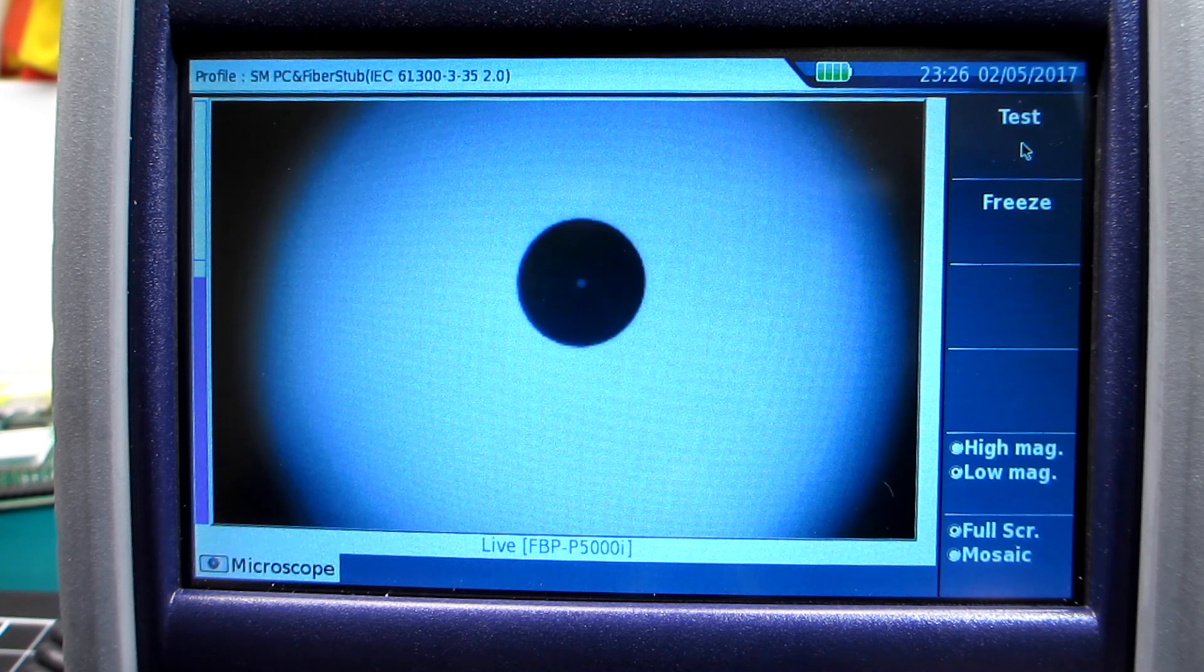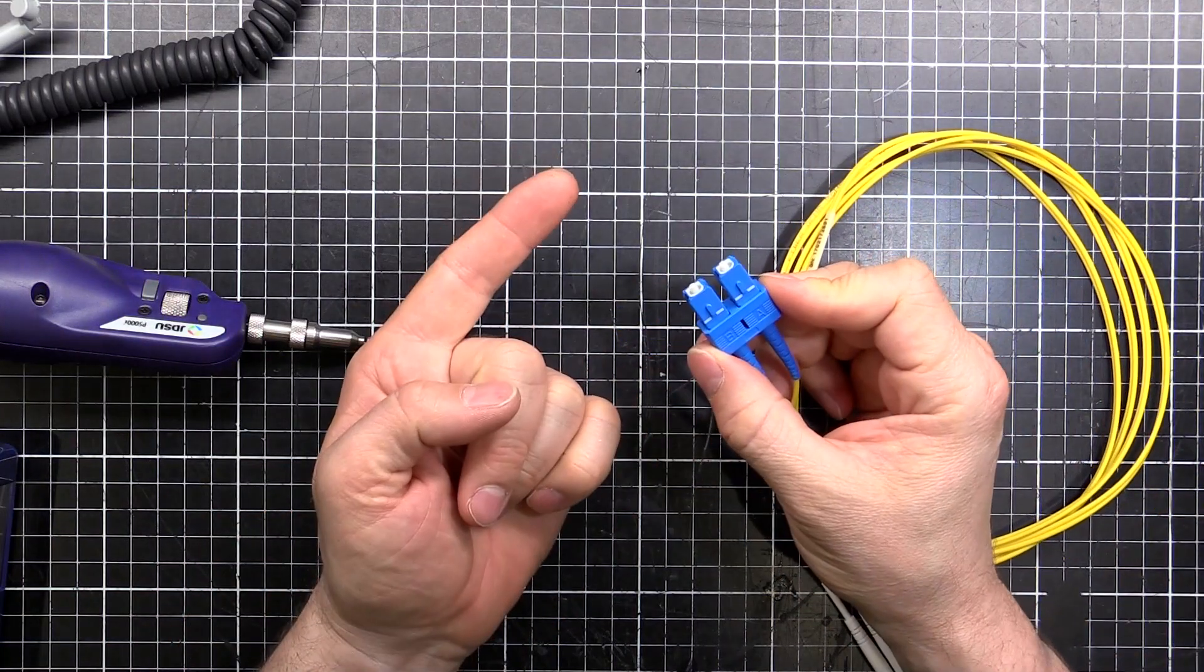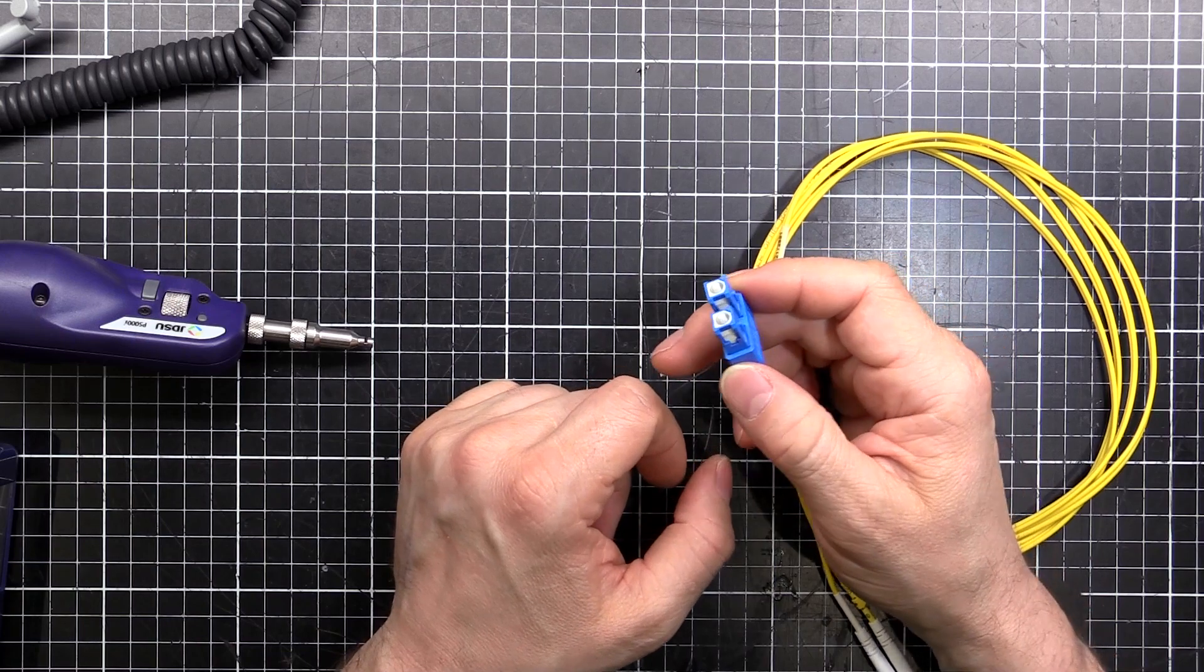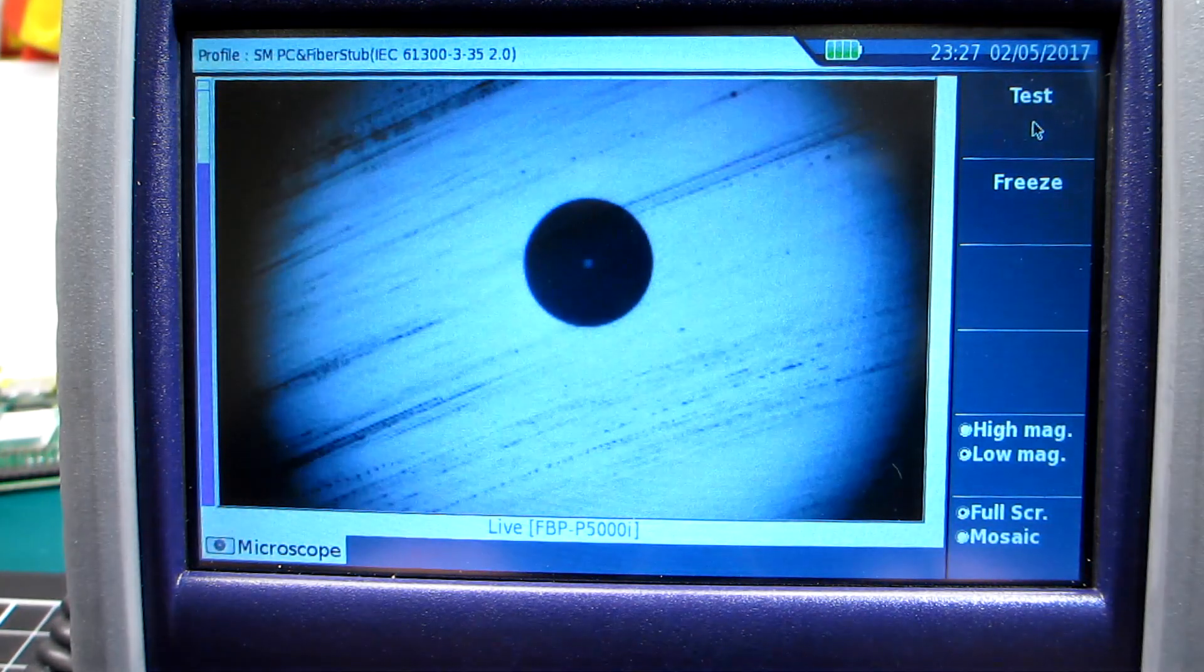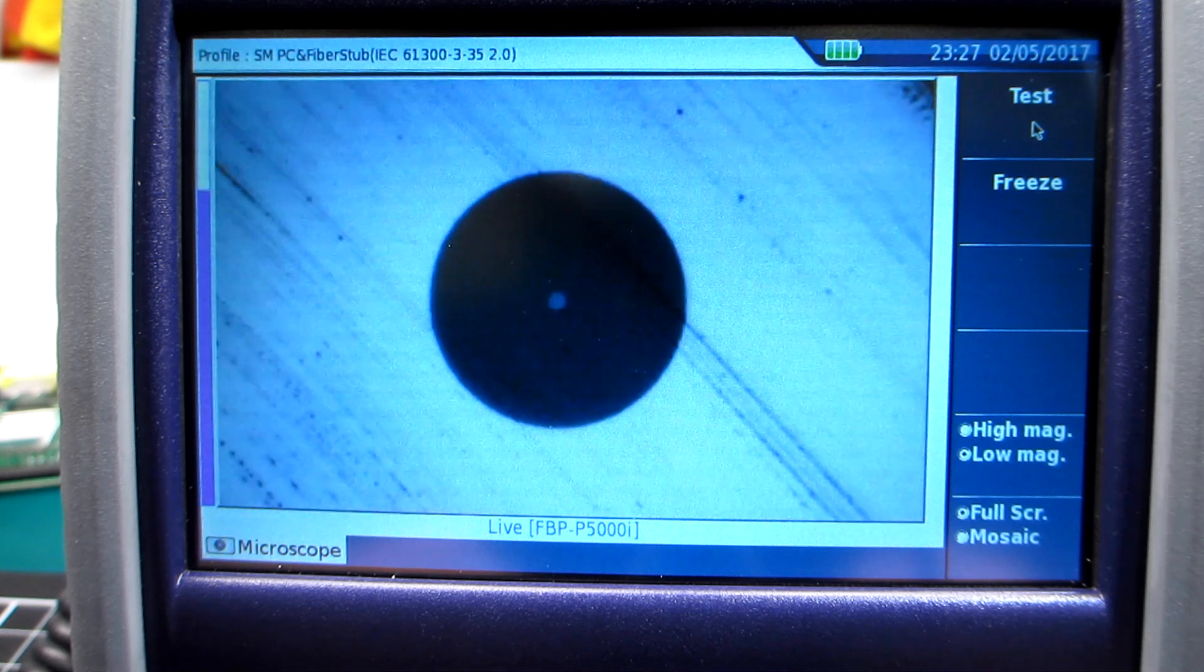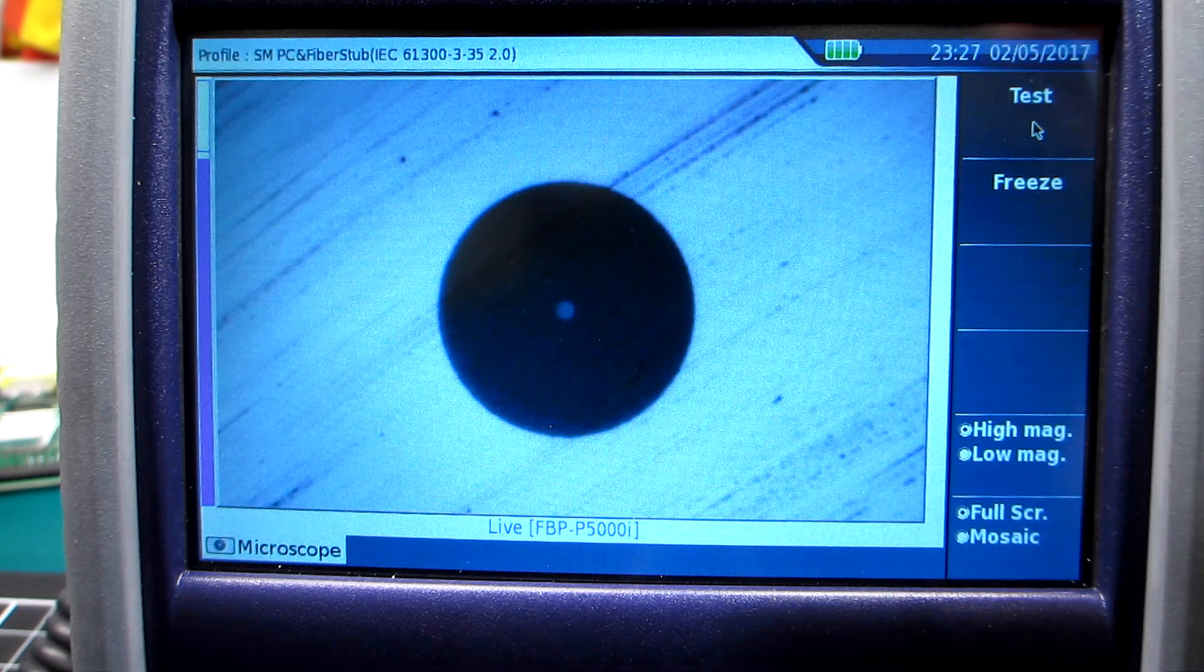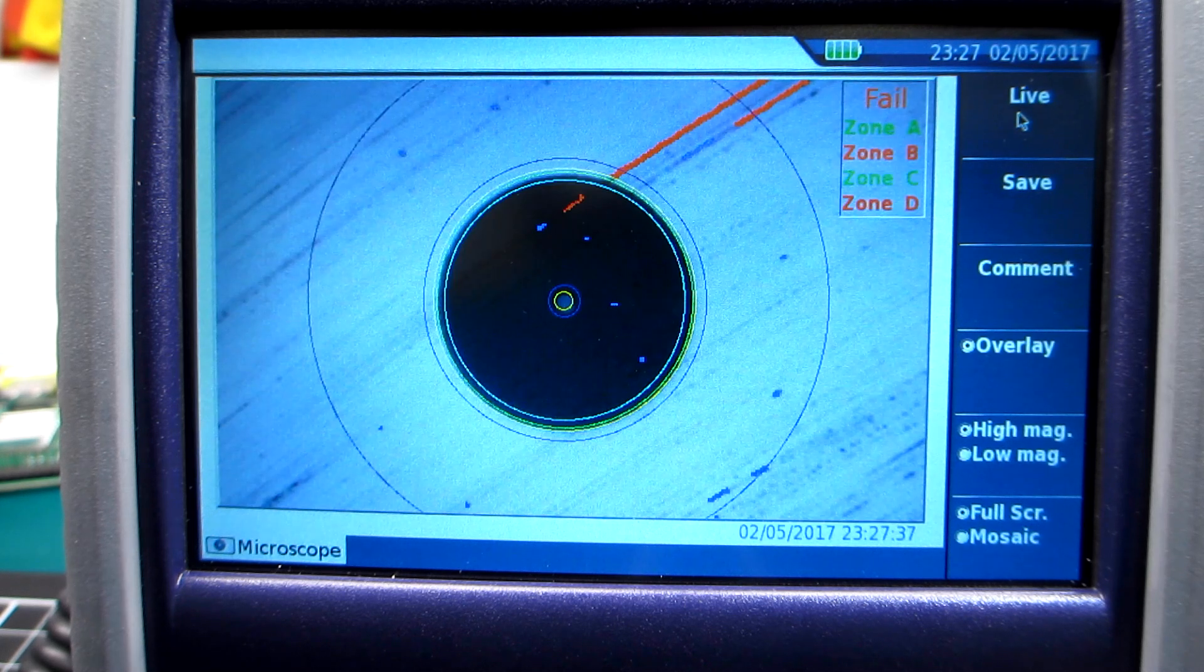Now I'll show you what happens if you touch these. So all I have to do, clean hand, just give it a touch. That's dirty. And that might even fail because it's going to be greasy streaks all over it. So let's look at that on the scope now. Yeah look at that. Oh dirty. I'll zoom in. Yeah look at those streaks. So let's give that a test. Give it a second. See what it says. Failed.